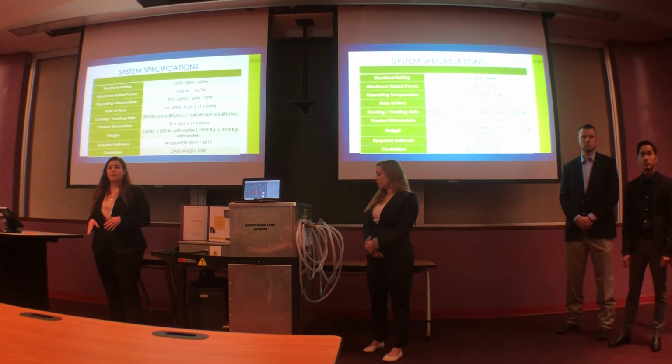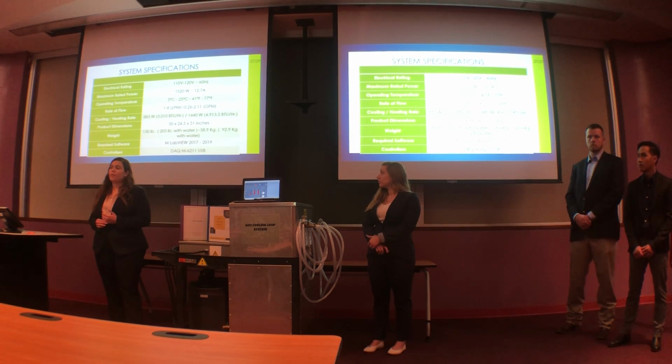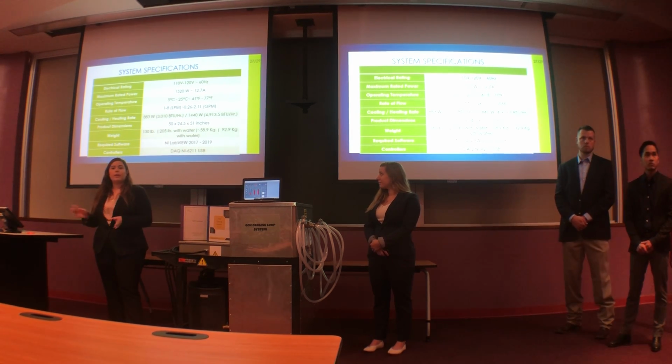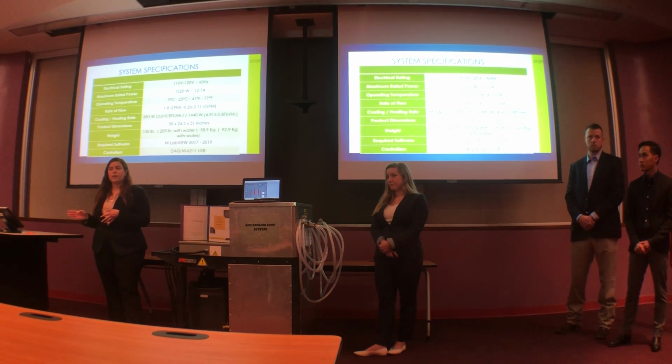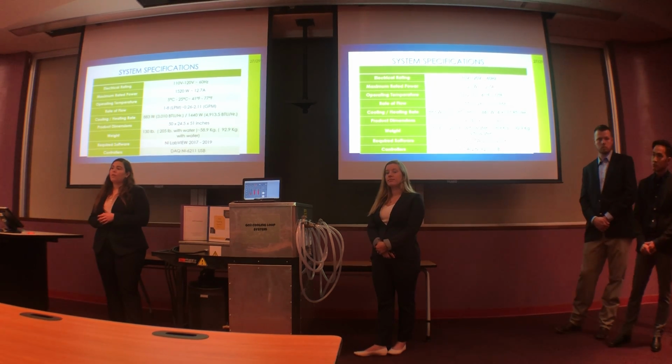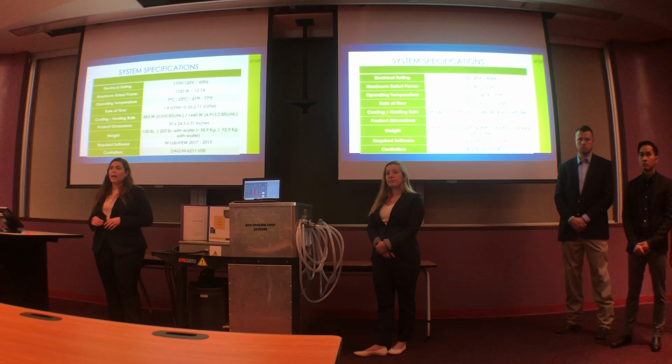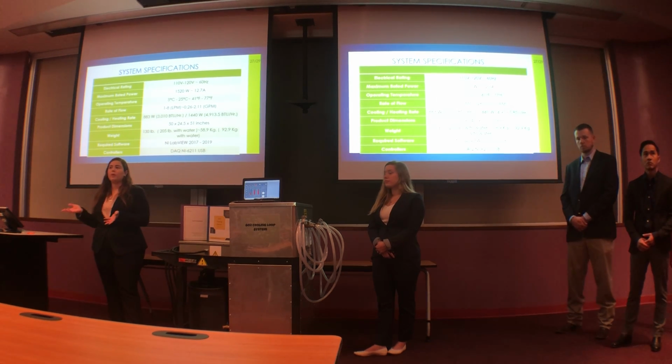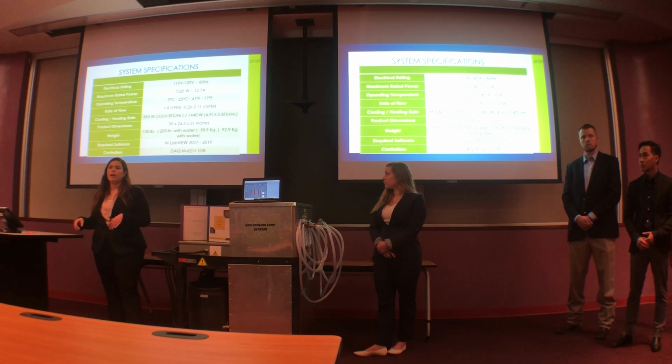The system specifications are an electrical rating from 110 to 120 volts, a maximum power of 1,520 watts, an operating temperature of 5 to 25 degrees Celsius, a rate of flow from 1 to 8 liters per minute, and we were using the LabVIEW software. And the weight of our system without water is 130 pounds, and with water is 205.